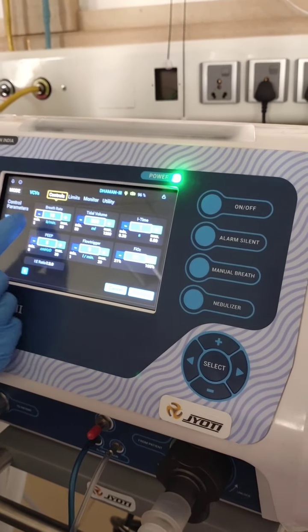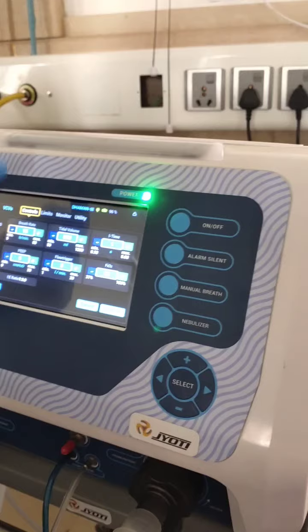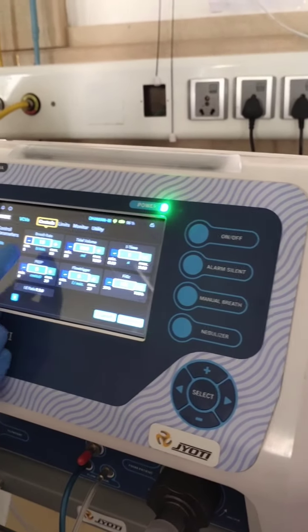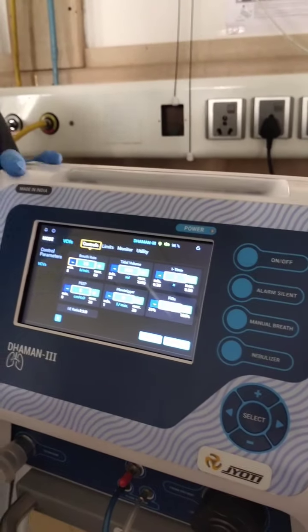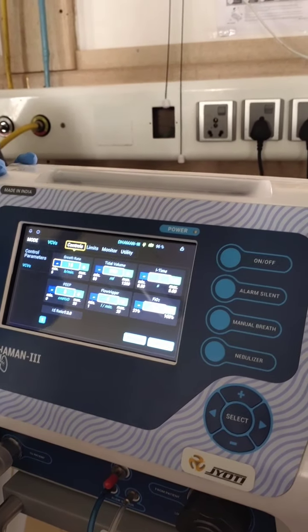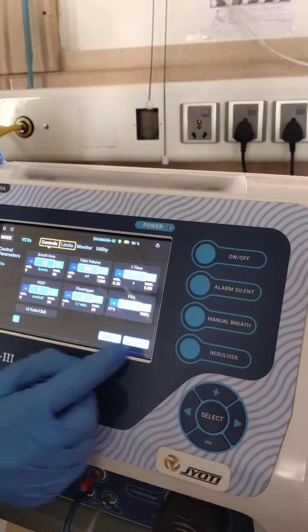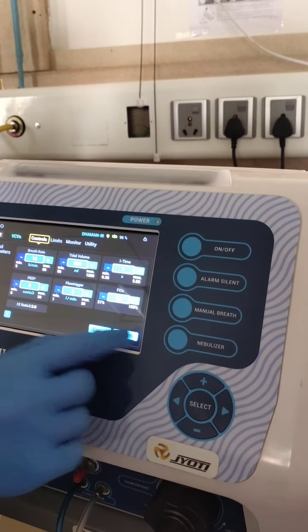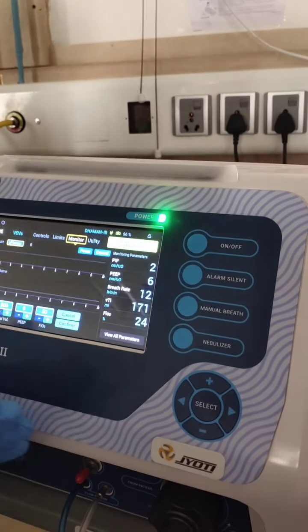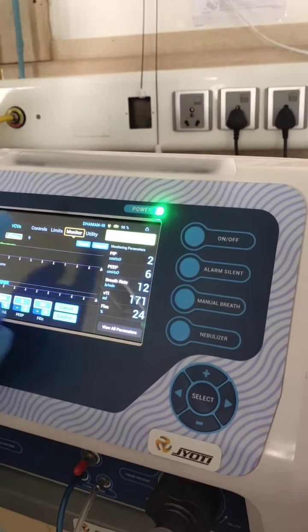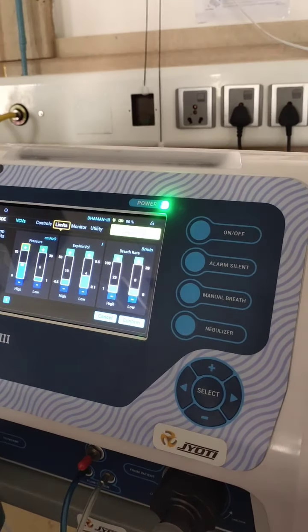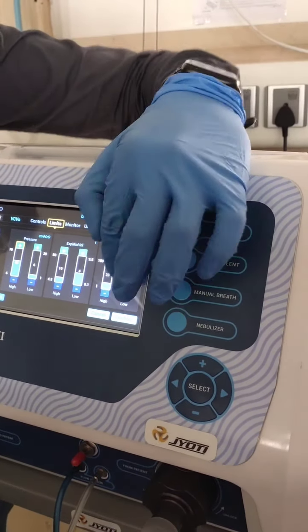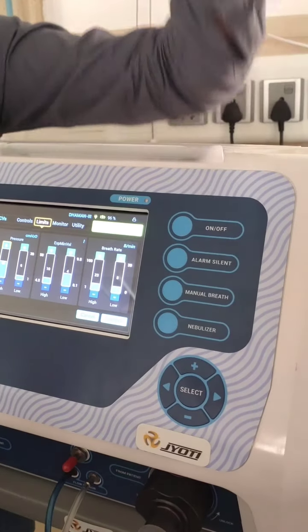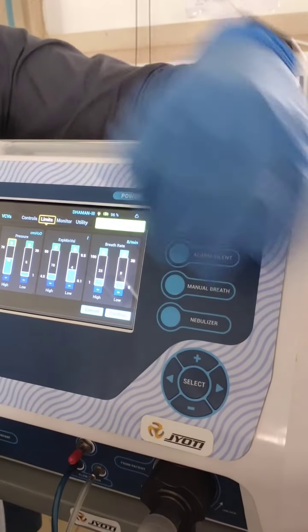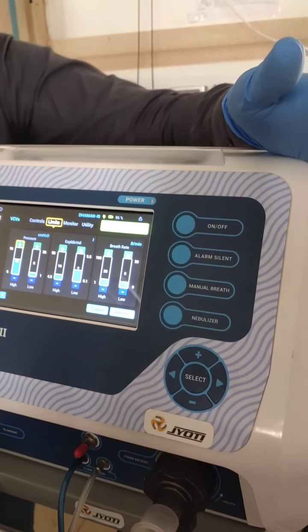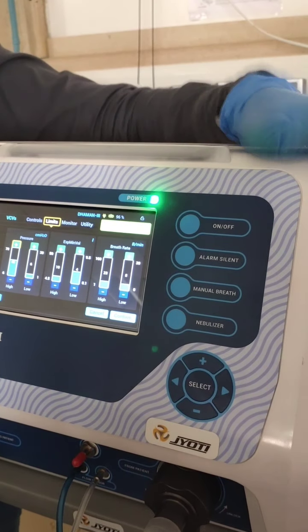You have to ensure that the minimum value does not cross the limit. If you are putting 50 for the breath rate, and you are giving 8 or 5, then the limit should be there. Okay, I will show. So this control, yes, I will confirm, yes. I said 5 and 50. Now go to the limits menu. In the limits menu, the breath rate will be 8 by default. If you are putting 6 or 5, it will show a low breath rate alarm. So you have to ensure that before you are doing the ventilation.